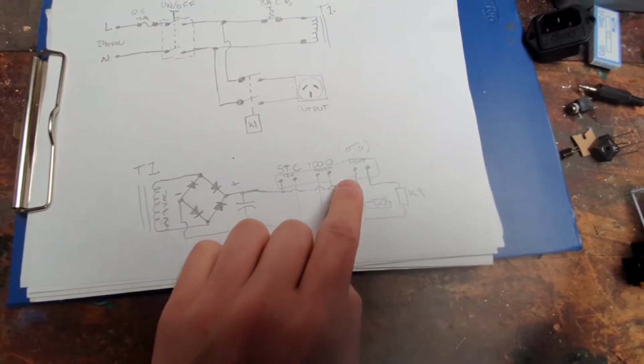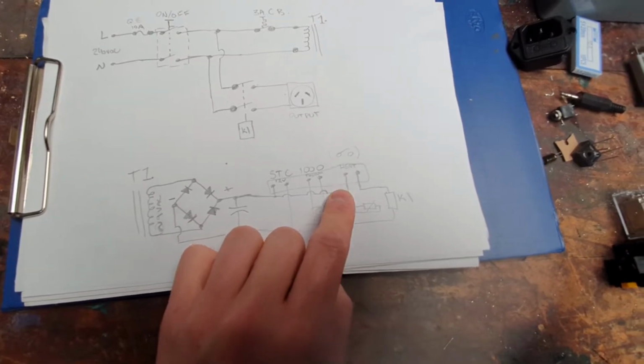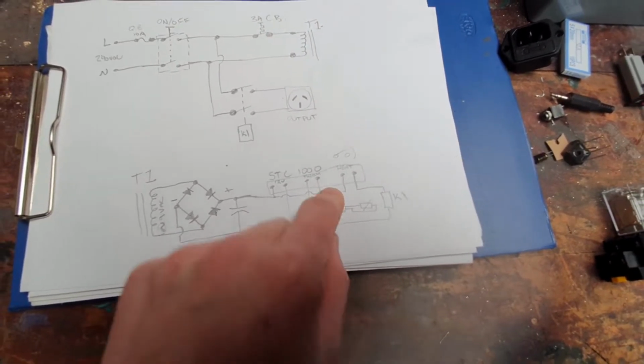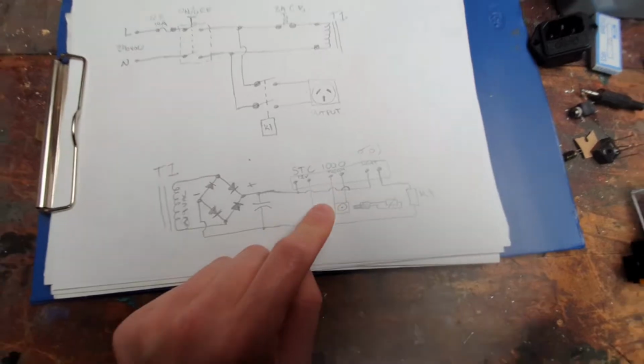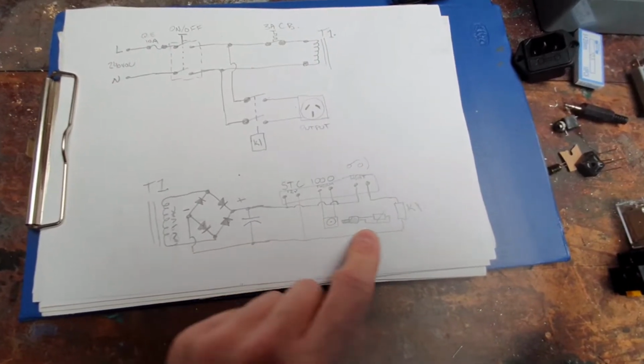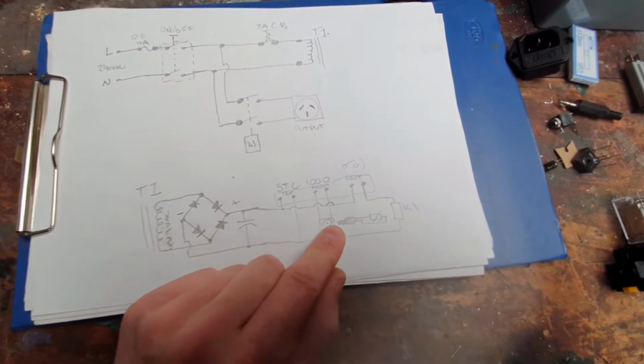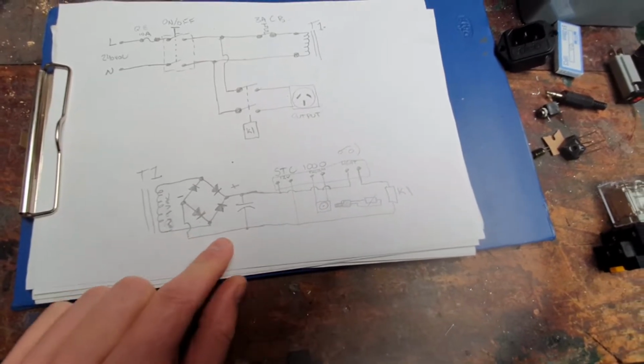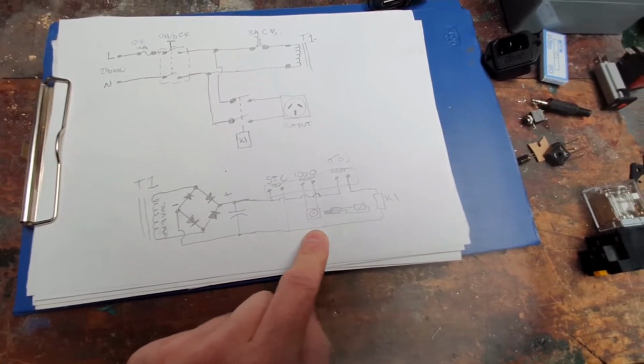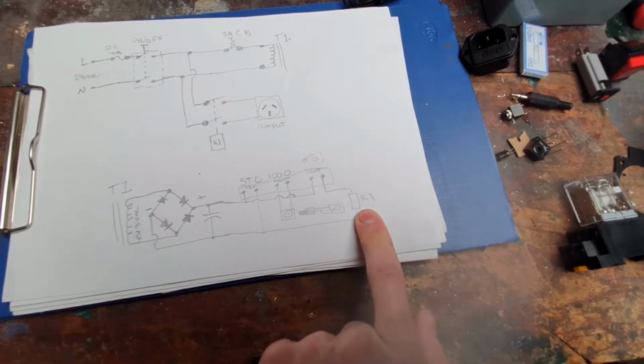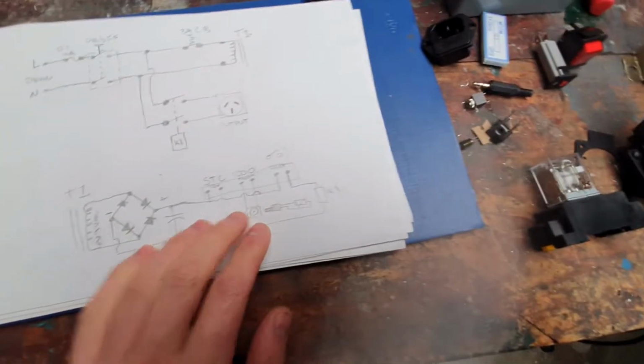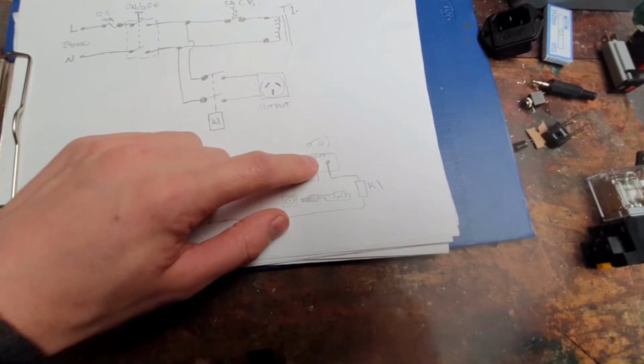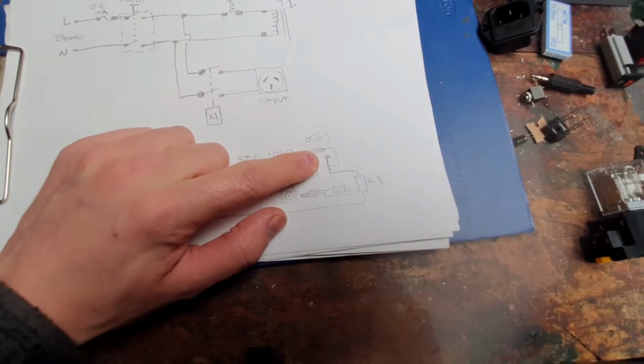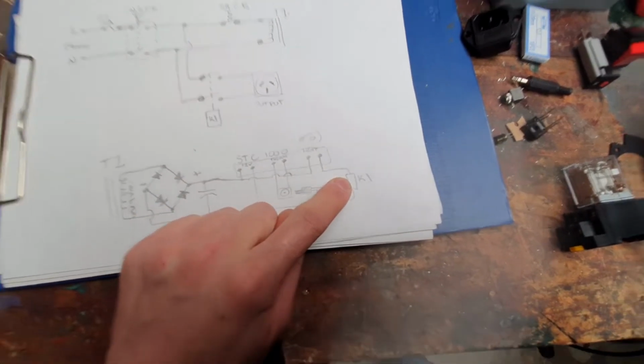And it also goes across to the heating relay. Obviously the thermostat is on its own little thing with the 3.5mm socket. The negative or common of the 12 volts goes to one side of the relay coil, this big relay, and then the switched side from the thermostat controller goes to the other side of the coil.